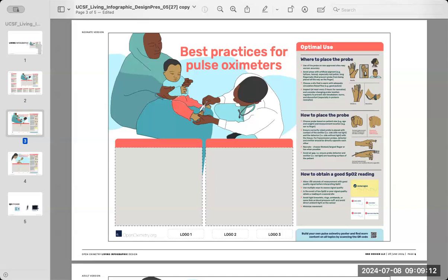So otherwise, if you look at the drawing panel where there are 4 panels to it, where it says where to place the probe, the bottom right-hand one is the better approach for an infant or neonate, where it's a wrap that goes around that part of it. So if you want to stick with an infant, and I support it very much because that's what my heart is, I would use a wrap, not Great toe clip. Okay, we'll make that adjustment.